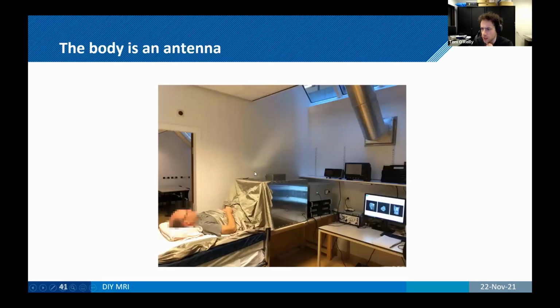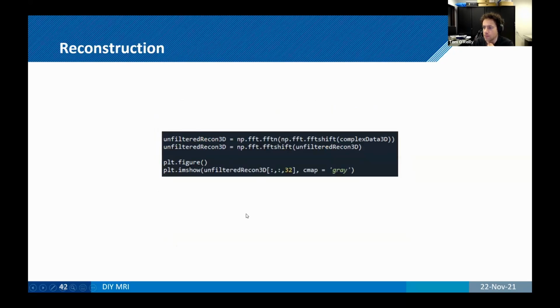It depends a lot on your coil design. We found that if we use a conductive cloth that we place over the patient and make sure that cloth is connected to the Faraday shield, then we virtually eliminate all that noise that's coupling in.